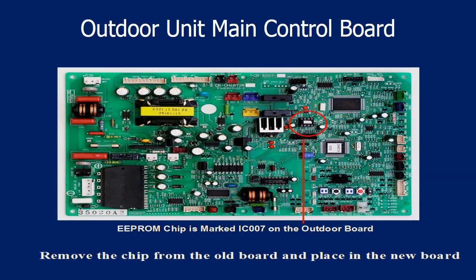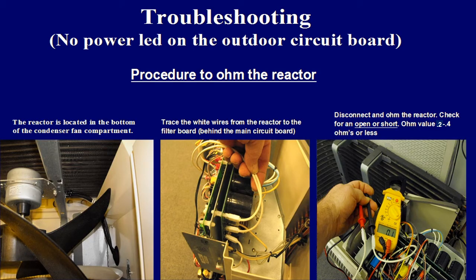When replacing the main control board on the outdoor unit, the old EEPROM chip must be removed from the old board and installed into the replacement board. If this procedure is not followed, the system will not operate. These EEPROM chips are also directional and have an identifying mark on one side of the chip. Also, transfer any jumpers from the old board over to the new replacement board. Once incoming power and all the fuses have been verified electrically, next locate the reactor within the outdoor unit. This electrical component is located in the base pan of the condenser right below the condenser fan motor.